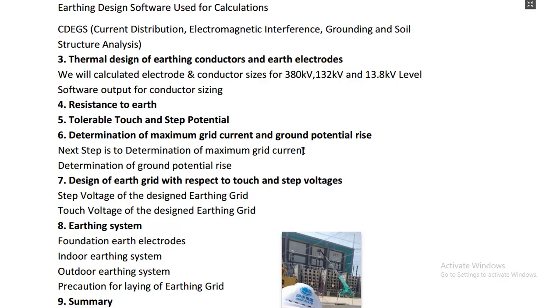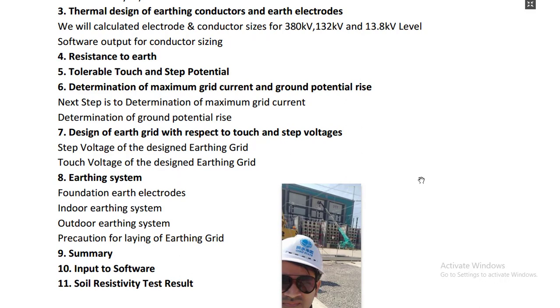The determination of maximum grid current and ground potential rise are the next topics. The short circuit level is provided by the client, and the grid is designed based on this. We will show the calculations for how the maximum grid current is determined. It is very important to know the short circuit level of your substation, which depends on how many transformers you have, how many lines are connected, the percentage impedance of the transformers, the source impedance of the line, and the source impedance. We will go through these calculations in detail.